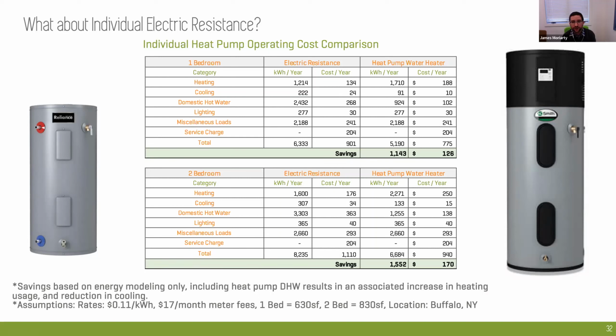The two things to note are the heating goes up. So it goes from $134 to $188 a year, because you're basically paying to heat the air that the hot water heater is stealing the heat from to put in the water. But you also get a reduction in cooling because you get a little bit of free cooling. I've heard it likened to having a small air conditioner running all year round. So you have to make sure that you can deal with the sound and deal with the temperature drop that comes with a system like that.